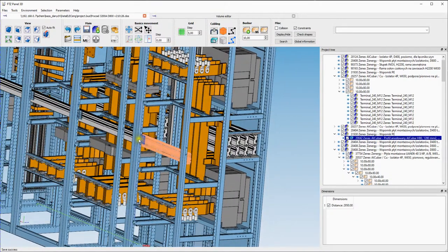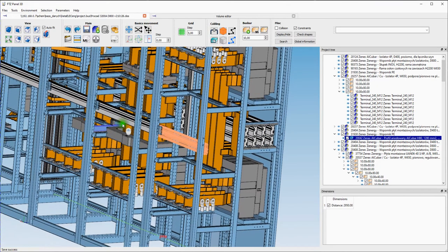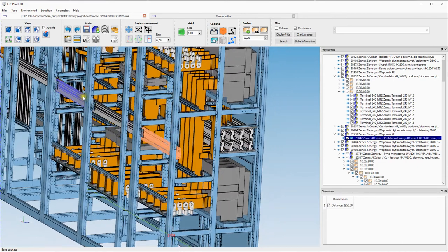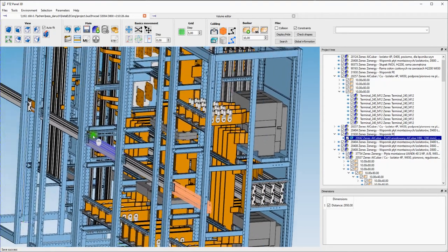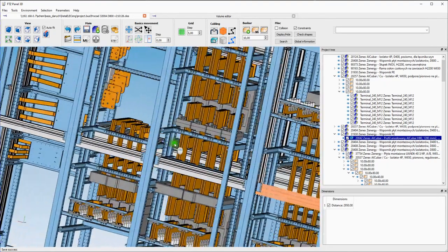The earth bus bar, the grounding, I made in the middle. I don't know where the cable comes from, top or bottom, so it is in the middle. Later in the cable compartment you can add a vertical bus bar, like here will be some cable compartment, we can add a vertical bus bar here.